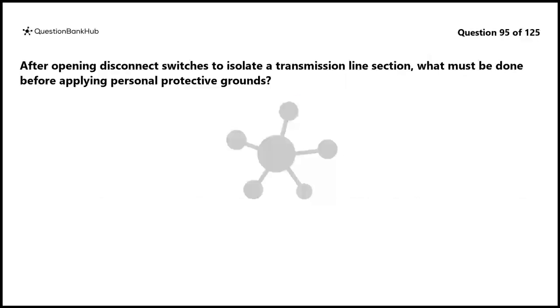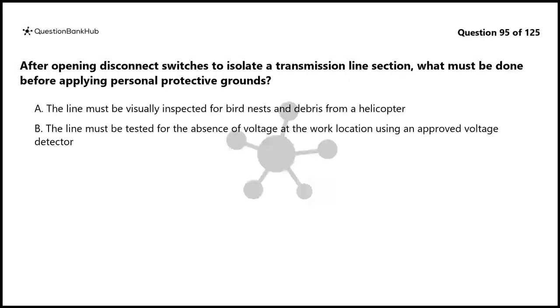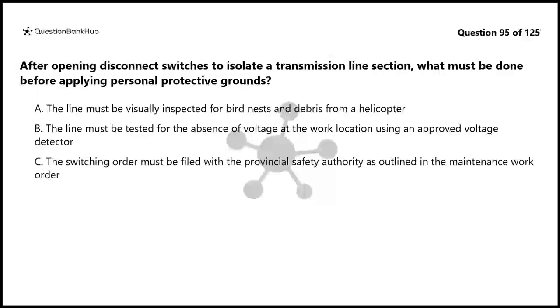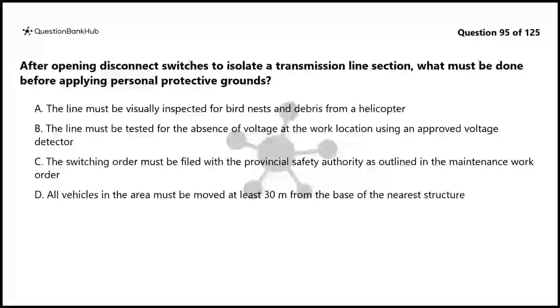Question 95. After opening disconnect switches to isolate a transmission line section, what must be done before applying personal protective grounds? A. The line must be visually inspected for bird nests and debris from a helicopter. B. The line must be tested for the absence of voltage at the work location using an approved voltage detector. C. The switching order must be filed with the Provincial Safety Authority as outlined in the maintenance work order. D. All vehicles in the area must be moved at least 30 meters from the base of the nearest structure.